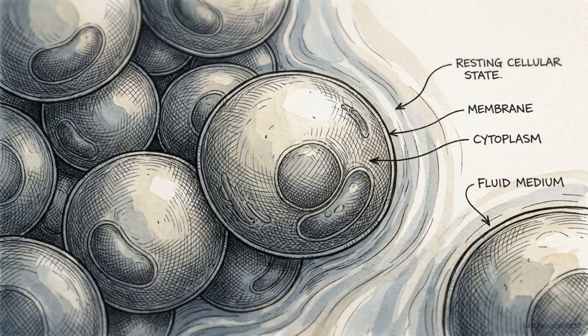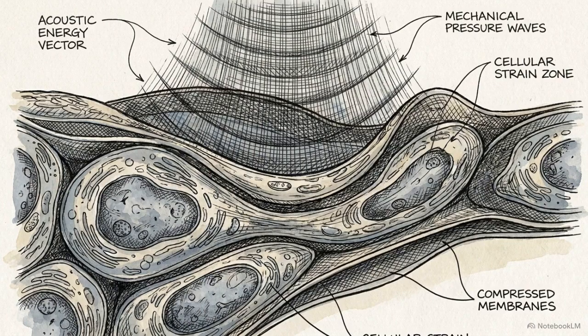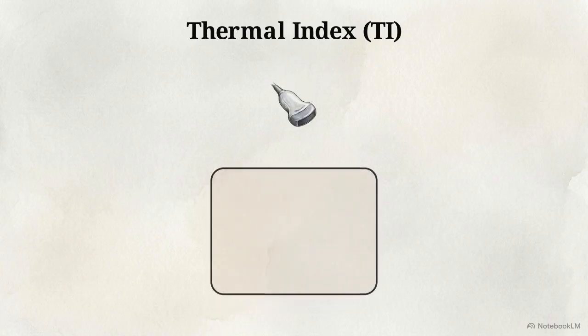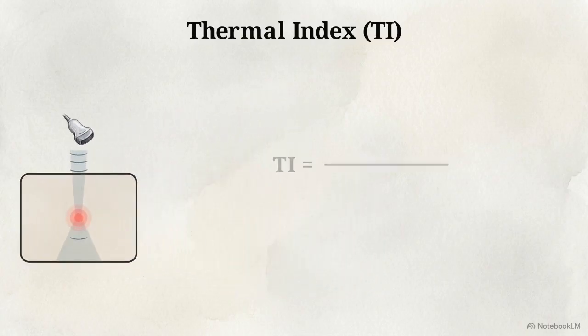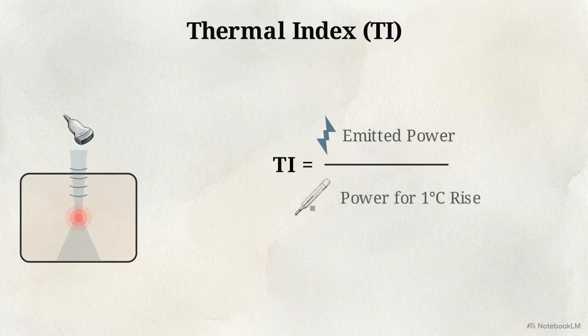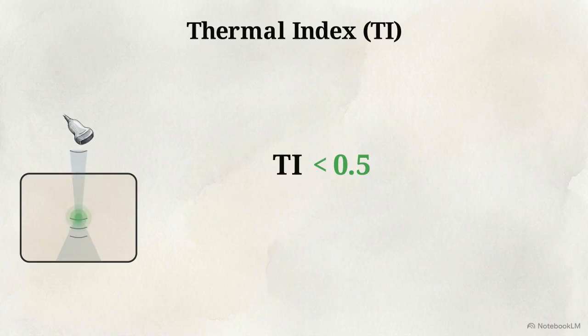Down at the cellular level, the physical reality of ultrasound becomes clear. Even without ionizing radiation, mechanical pressure waves force energy into tissue, causing biological strain. This diagram outlines the first major risk metric, the thermal index, or TI. This measures the ability of the acoustic beam to induce localized heating in human tissue. The index is a strict ratio. It divides the emitted acoustic power by the exact power required to raise the local tissue temperature by 1 degree Celsius. For routine clinical scanning, a thermal index below 0.5 is considered entirely below the threshold for any biological effect.